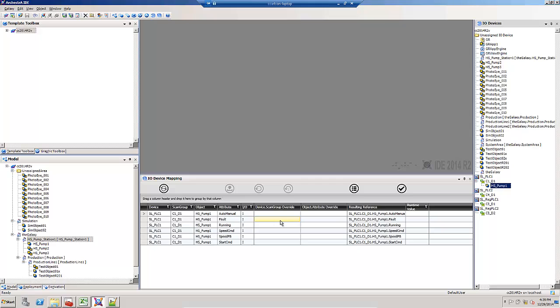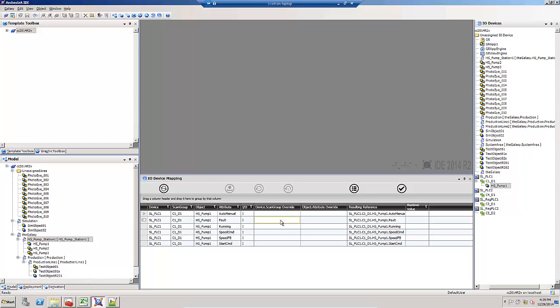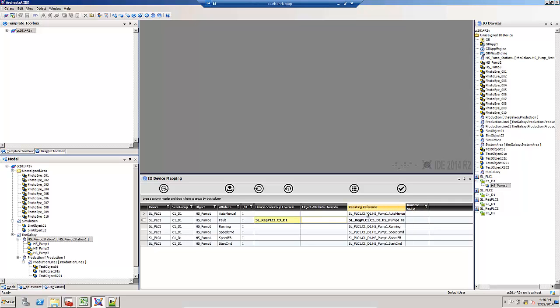Notice these two override columns. Let's override this fault. Let's say that it comes from a different PLC than what the rest of the attributes come from. I can type an override in here, and I'm going to give this one of the other DI objects that I have.